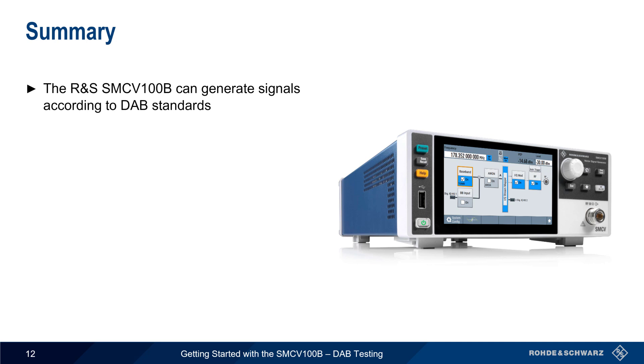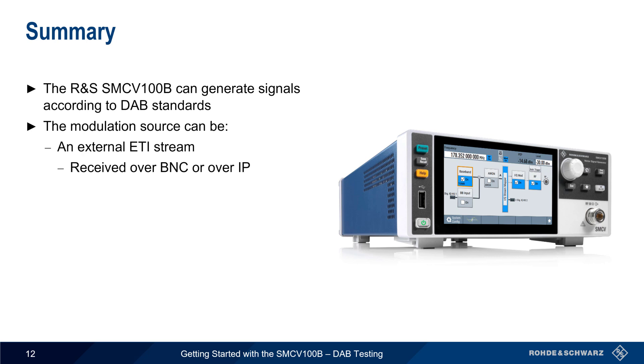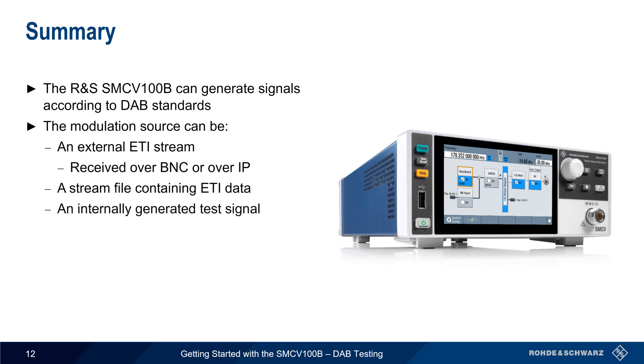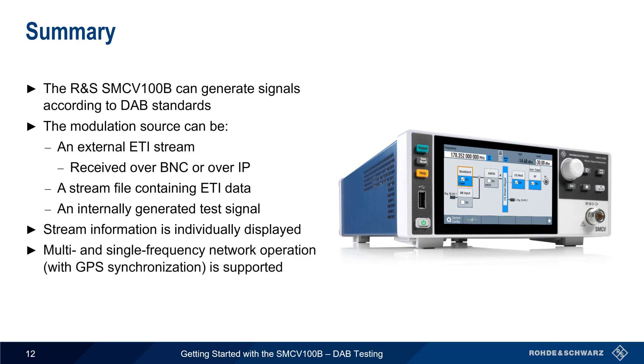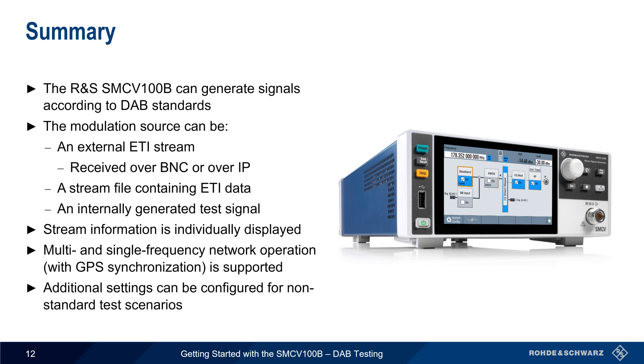In summary, the Rohde & Schwarz SMCV100B vector signal generator can be used to generate signals according to the Digital Audio Broadcasting or DAB standards. Three different modulation sources can be used: an external ETI stream fed in over a BNC connector or via IP over the LAN interface; a stream file containing ETI data using predefined stream file libraries; or an internally generated ETI test signal. Once a source is configured, information about each stream is displayed in real time. The SMCV supports both multi-frequency and single-frequency network modes, with GPS synchronization for single-frequency networks, and allows configuration of additional settings for non-standard testing scenarios.